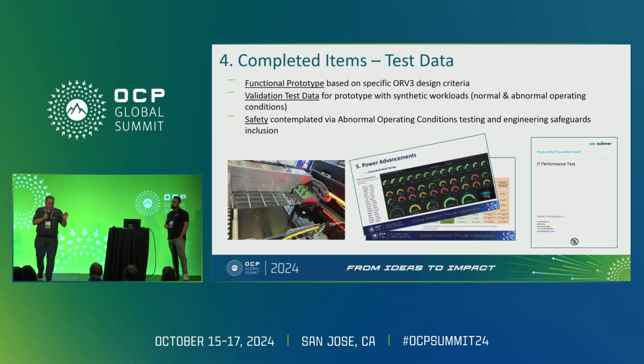It works very well. We also want to be careful about safety. This is an interesting thing because UL and their counterparts haven't quite caught up with us. So what we're doing is making sure that we meet all the air requirements, plus we're putting it in fluids and testing, making sure everything still works. All the air requirements allow it to shut down safely - you can't short it out, you overcurrent, it still shuts down. So we're making sure nothing gets changed because we're using it in fluid. That's what we're working on so that we can show the agencies, show people, hey, this is what we found, this is what we want, so they can create specific test criteria, because there is none really today.